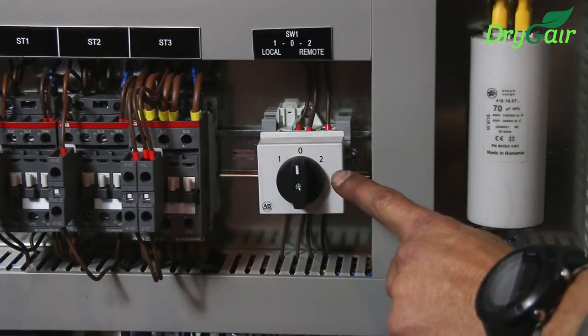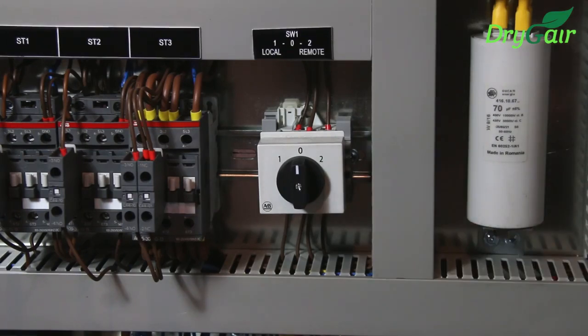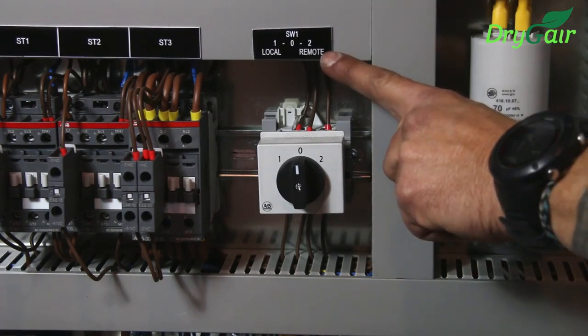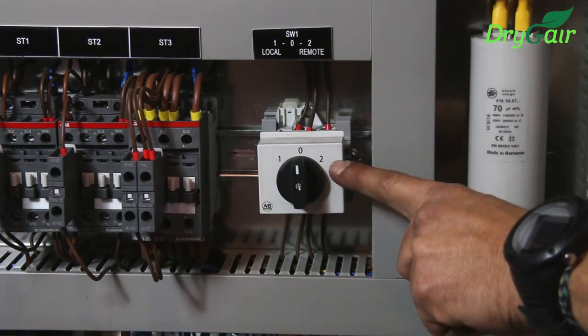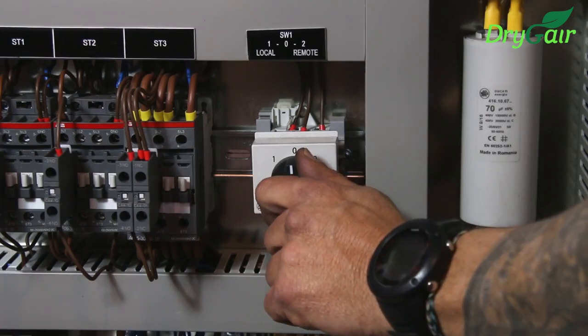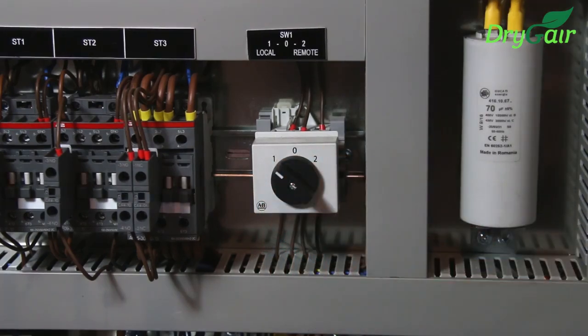It has 3 operating modes. When set to 0, the unit is in disconnected mode and is off. When set to 1, the unit is in local mode and operates according to the values set in the temperature and humidity controllers. When the unit is set to 2, it's in remote mode and is operated and controlled by the climate control system. We will now turn the unit on to local mode.